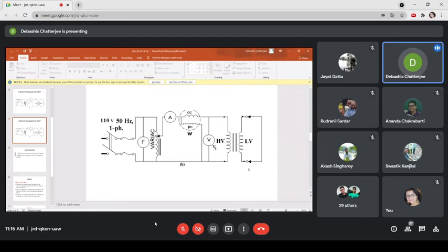You should apply a voltage which will cause a current of the order of the rated current. You can go up to 110% of the rated current, just to see the characteristics up to and beyond the rated current. So the voltage applied should be less.